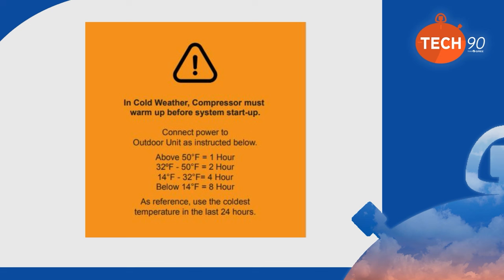The reason I say as close to it as possible is, maybe it only takes you 4 hours to do an install. That's great. I was never that fast, but I'm a pretty big boy and I don't move real fast anyway. But the very first thing we would like you guys to start doing, and I'm guilty of it too, is this: whenever I did installations, the last thing I ever did was apply power to that outdoor unit. That was the very last step in the entire installation process.